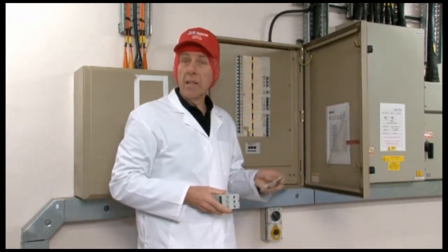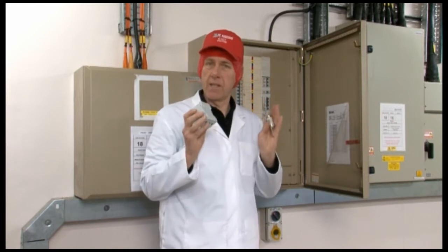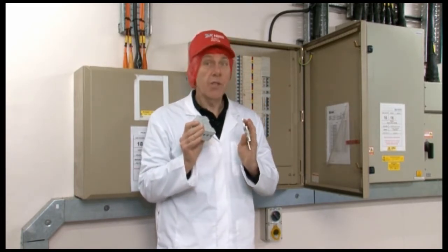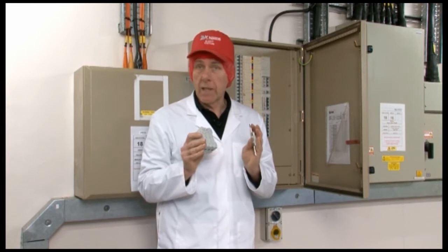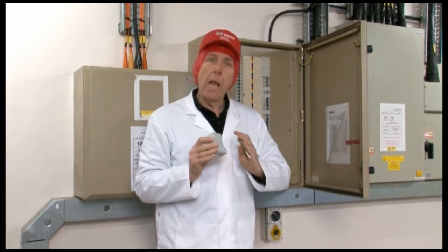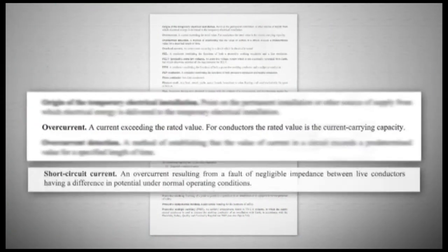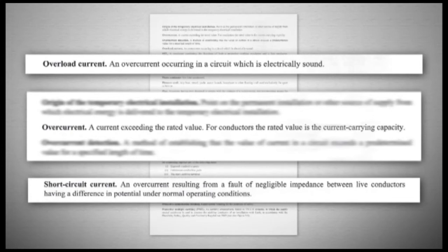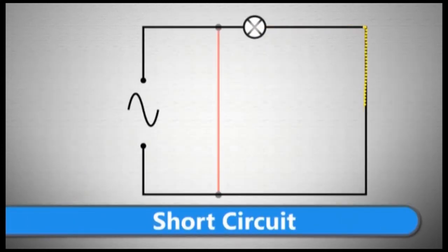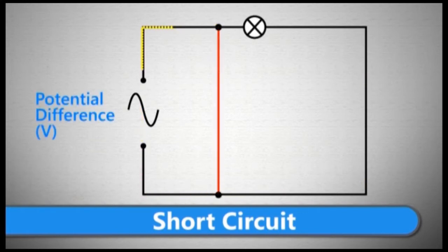Regulation 11 gives legal status to protective devices. Efficient means, suitably located, shall be provided for protecting from excess of current every part of a system as may be necessary to prevent danger. Excess current, or as it's referred to in the IET wiring regulations, overcurrent, can arise from either short circuits or overloads. In the case of short circuit, just how large a current will flow depends on the potential difference between the two conductors and the resistance of the fault loop.